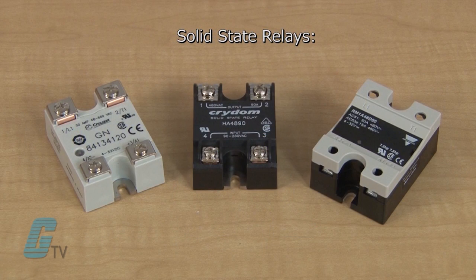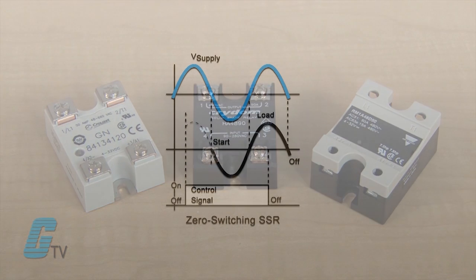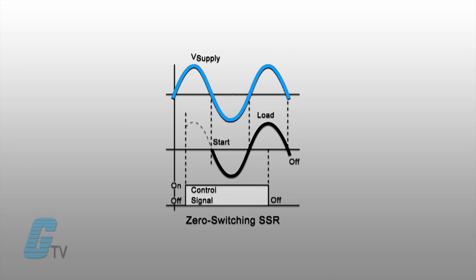A few different types of solid state relays are zero switching, instant on, peak switching, and analog switching. The most common solid state relays are zero switching relays, which turn on the load when the control voltage is applied and the load voltage crosses the zero point of the AC sine wave. The relay turns off the load when the control voltage is removed.